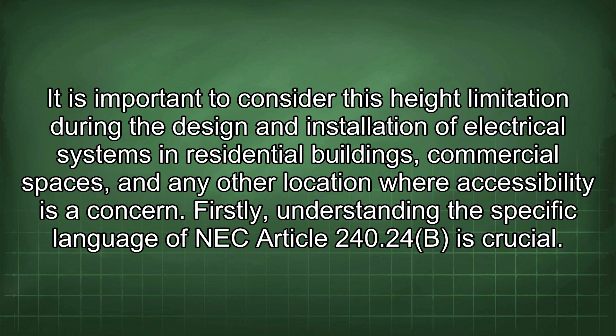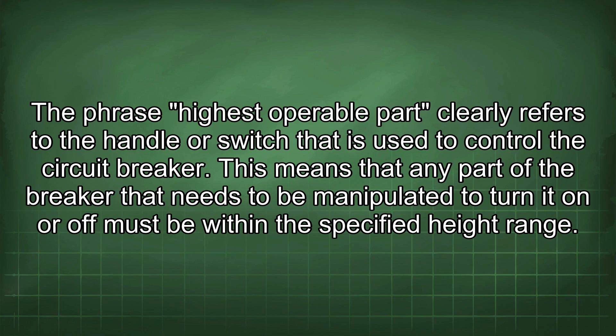Firstly, understanding the specific language of NEC Article 240.24(B) is crucial. The phrase highest operable part clearly refers to the handle or switch that is used to control the circuit breaker. This means that any part of the breaker that needs to be manipulated to turn it on or off must be within the specified height range. Secondly, the height measurement is taken from the finished floor or working platform. This is the surface on which a person would stand or from which they would operate the circuit breaker.